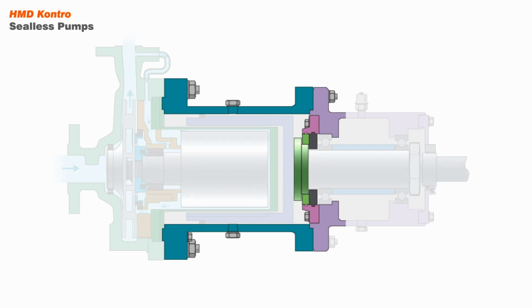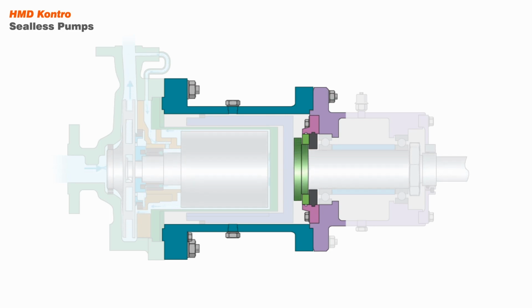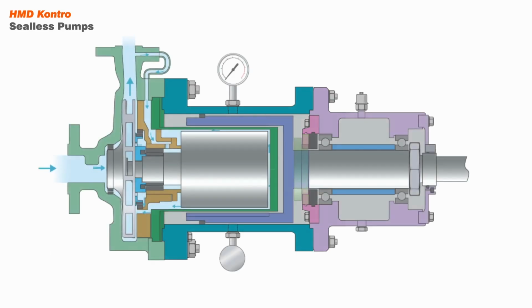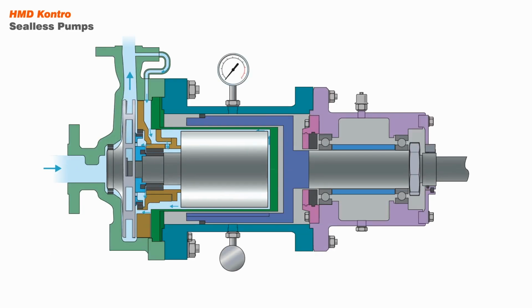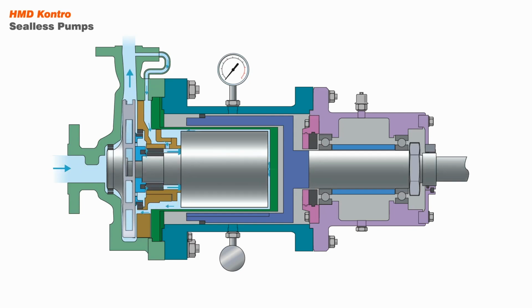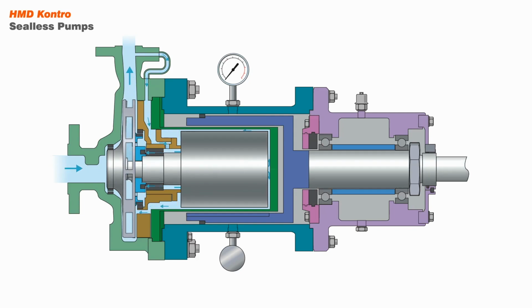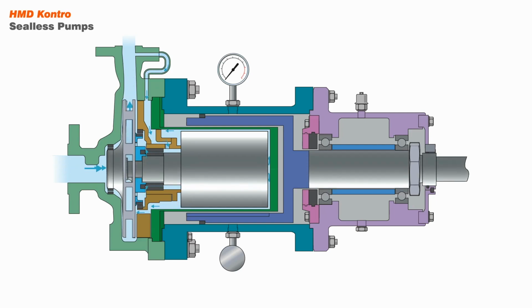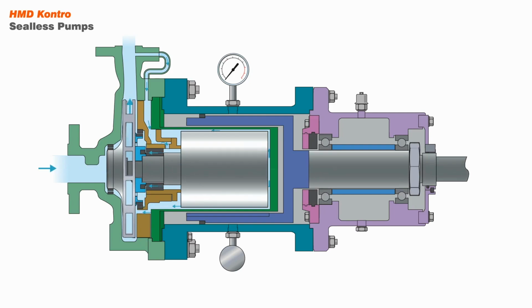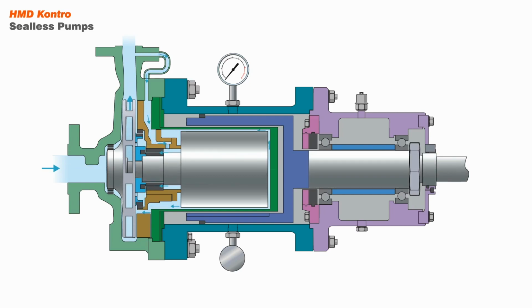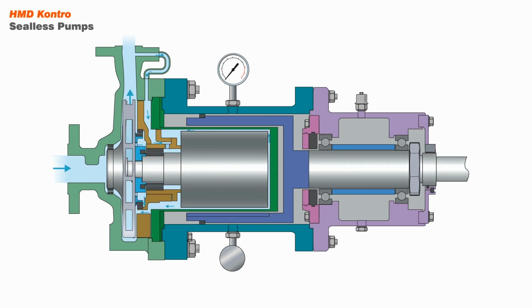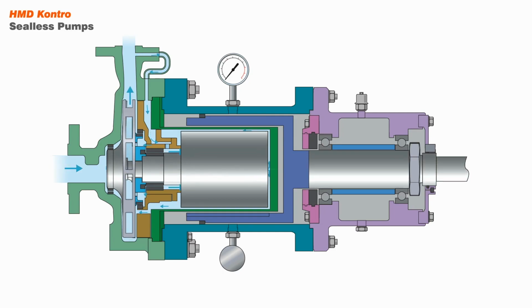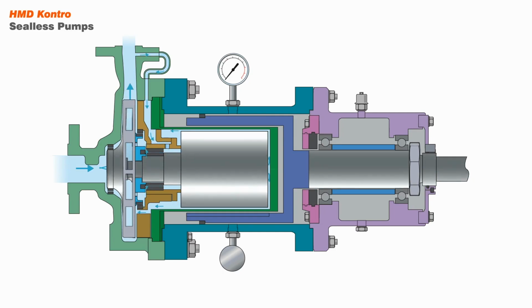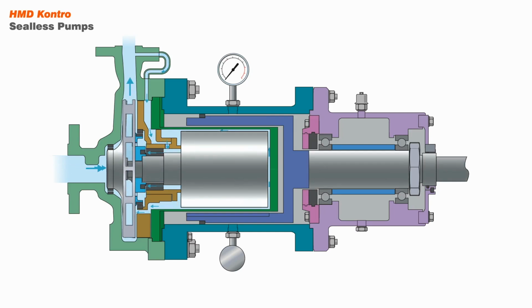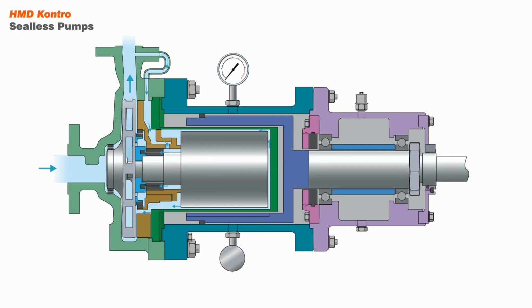In the unlikely event of a primary pressure boundary failure involving the containment shell, process liquid is contained within the secondary pressure boundary. With the secondary containment design option, a level of pump instrumentation is needed to alarm and shut down pump operation should a primary pressure breach occur. This instrumentation comprises a pressure sensor and/or a liquid sensor fitted to the magnetic coupling housing. For low vapor pressure liquids, a liquid sensing probe is used. For high vapor pressure liquids, a pressure sensor. These need to be set to stop the pump immediately if a leak is detected.